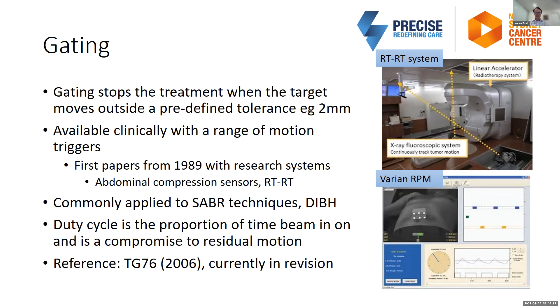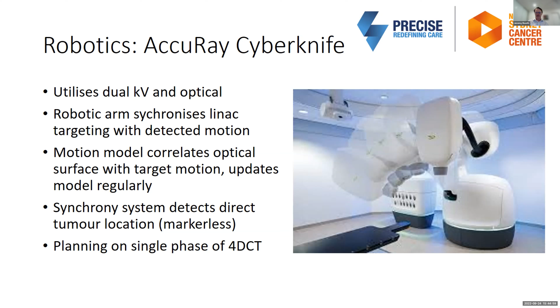The predominant commercial system is the CyberKnife. This is an old picture, but the system has dual kV imagers and an optical system. It has a robotic arm that synchronizes with the targeting of the detected motion, and it creates a motion model that enables it to track the motion without requiring additional X-rays. The more recent innovations are that it does not require fiducials in all cases, particularly for lung cancer and some of the other indications.